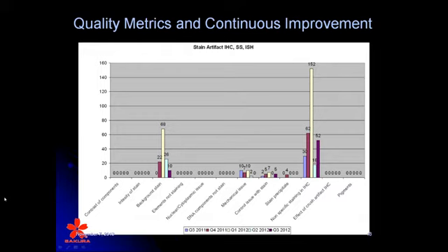And here we're able to provide quality metrics on our IHC, where we're starting to see nonspecific staining. In this issue right here with the nonspecific staining and background staining, we found a lot of issues with the kits that we received from our vendor for our immunohistochemistry. And by doing this, we were able to give them real-time perspective of, hey, we have a situation. And quite frankly, about 2 to 3 months after we gave that information, not saying we were the cause, but we were confirmed when the vendor sent us a letter stating that there was a variance in their lots and that we needed to go ahead and take a look at the situation.